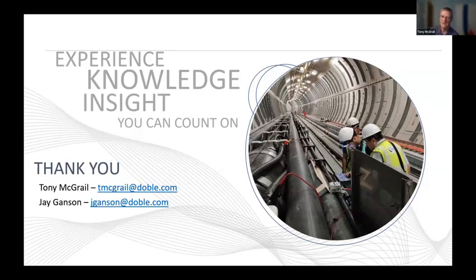I think maybe that's what he found. We didn't find that. But there's a technical brochure from CIGRE a few years back, technical brochure 642 on transformer reliability, and that one found very little evidence of a bathtub curve for most of the organizations involved. So I'm not saying Chris is wrong. I'm saying in his case, he found it to be applicable. But in the case of National Grid US, we did not, and in the case of National Grid UK and many other utilities, it didn't seem to apply. So when Jay showed his little chart of a bathtub curve for cables, the first thing I did was step back and ask, are you sure about this bathtub curve? Do we know it applies? What are the age-related failure mechanisms which we can demonstrate or find that would apply to cables? It may be that they do have age-related failure mechanisms, but they still need that failure mechanism to apply and be in service. So that's my little spiel on bathtub curves.